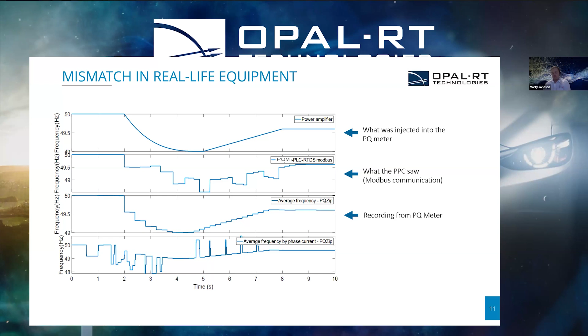There are a number of different challenges we see on site: incorrect frequency measurements, like we just saw. We've also seen that power quality meters sometimes have variable delays, which is something we don't capture in modeling. Sometimes a meter will respond in 30 milliseconds or 5 milliseconds, but sometimes we can see it up to 200.